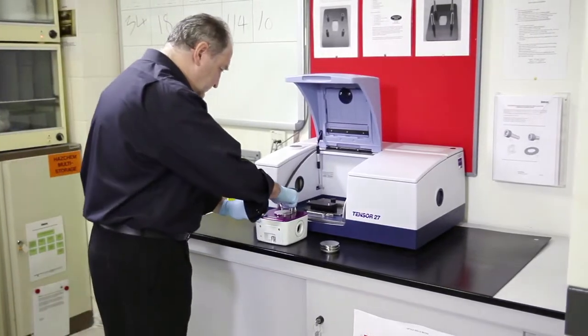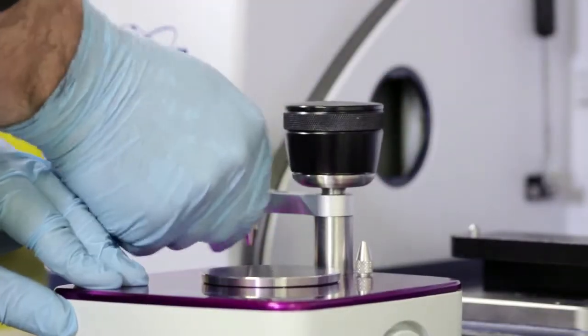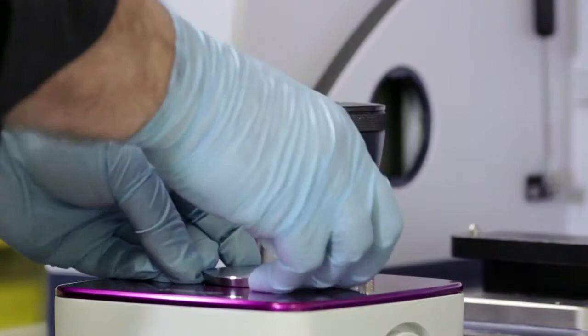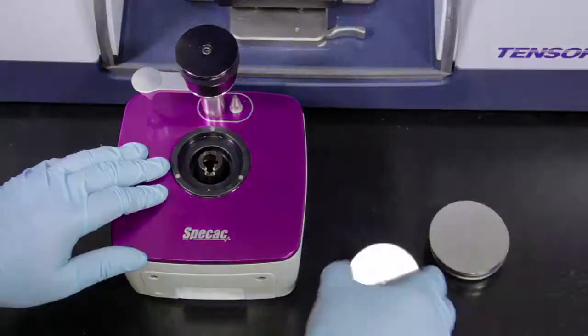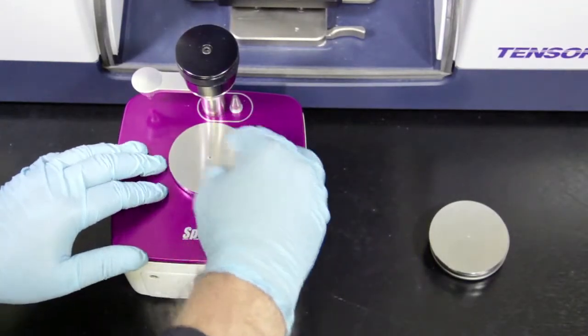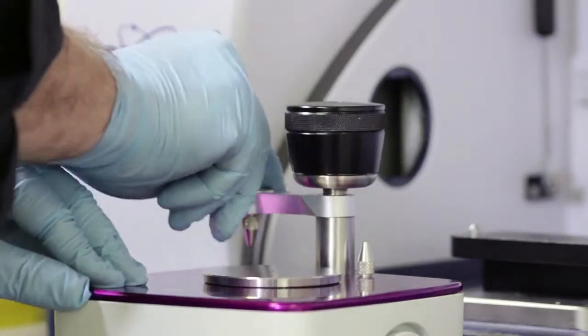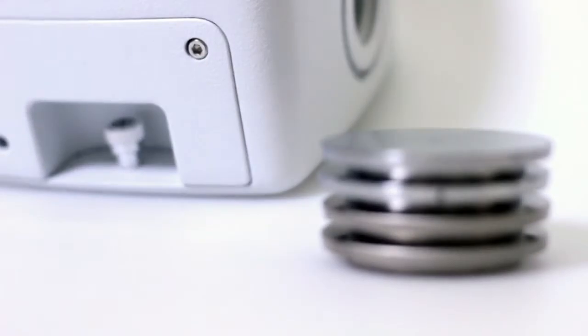Interchangeable ATR crystal pucks easily fit upon the optical unit and are magnetically held in place. A choice of four crystal pucks are available for the Quest, including two configurations of strong and durable monolithic type 3A diamonds, a zinc selenide and germanium crystal option.